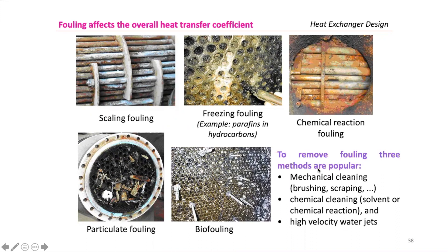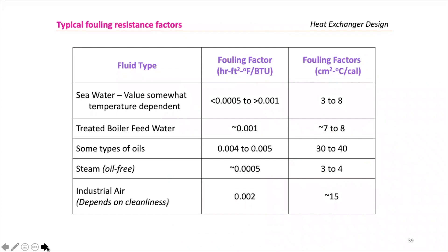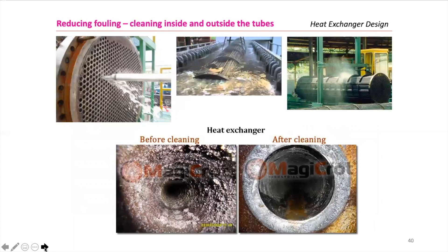There are three popular methods to remove fouling: mechanical cleaning (brush and scraping), chemical cleaning (solvent or chemical reaction), and high-velocity water jets. Fouling resistance values are available for different types of fluids in your Chapter 12 tables. When selecting fouling factors from tables, we typically use the bigger one — we over-design all the time.